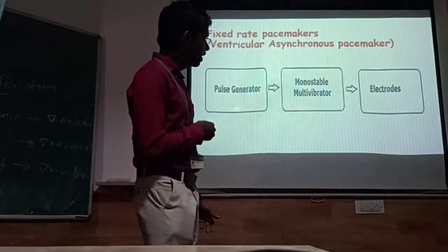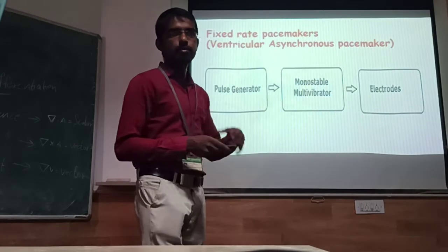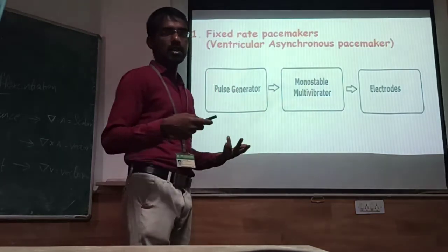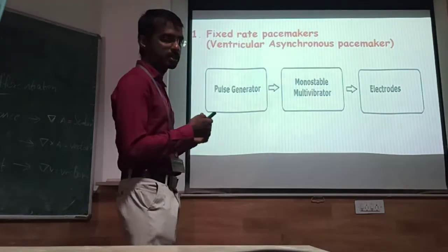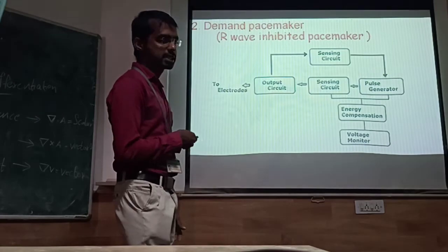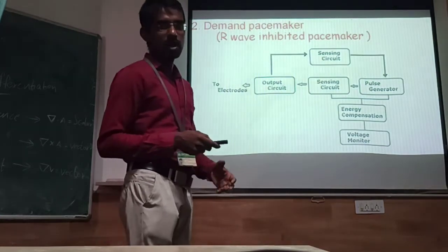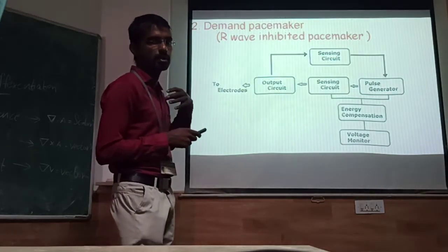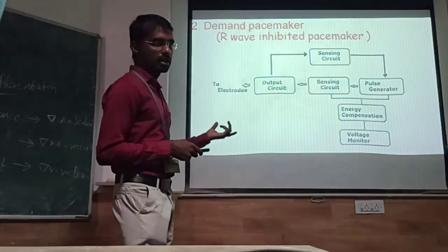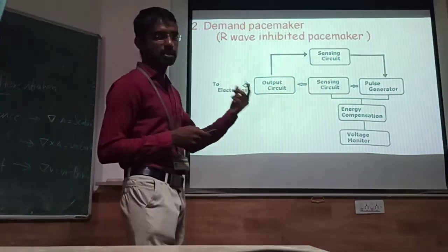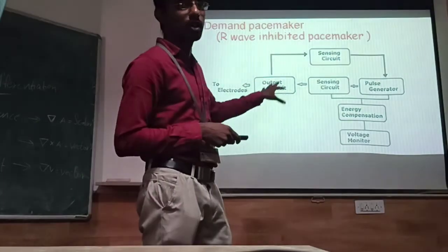See, the more you operate continuously, the more the battery is going to be drained. The lesser you operate, the longer the lifetime of the battery or the circuit will be. So our agenda is to increase the battery time. Also, natural pacing is always better than the artificial one. That's why we rely on the natural pacing done by the sinoatrial node. Whenever there's a problem, then this entire circuit will work.